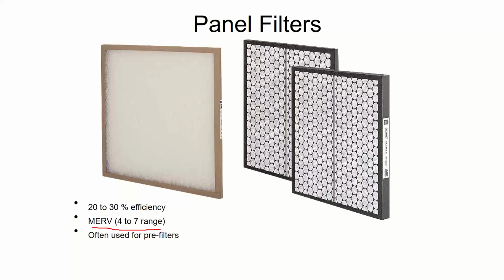Nowadays, more modernly, we'd also like the filter to catch germs. That would be great if we can do both. This filter can't do both. This is a crappy filter. I would use this kind of filter only in one of two scenarios. One, it's construction time. They're still building the building out. There's drywall dust and crap like that I want to catch. But I don't want to put the good filter in yet because that thing's expensive. So I'll put these cheap ones in temporarily. Or two, I will put one of these cheap ones in as a pre-filter to catch all the big stuff. And I'll have my good expensive filter after that. And that way I don't have to change it as often. It'll last longer because the big, good, expensive filter can spend its time catching small things because this sacrificial lamb upstream caught the big things.